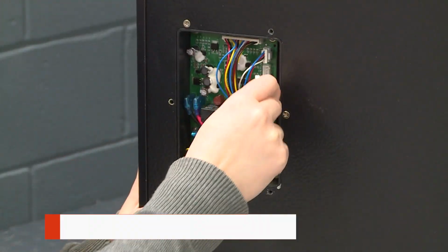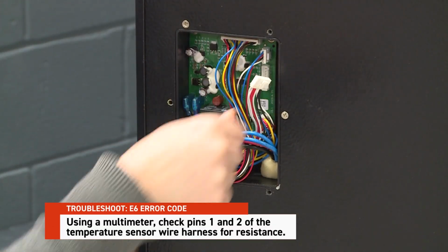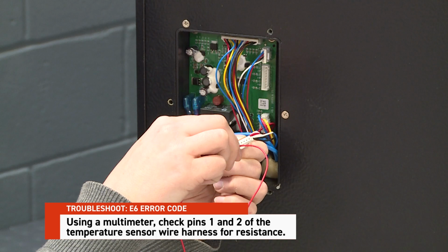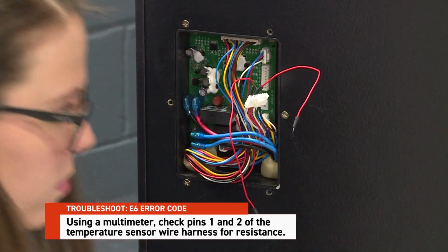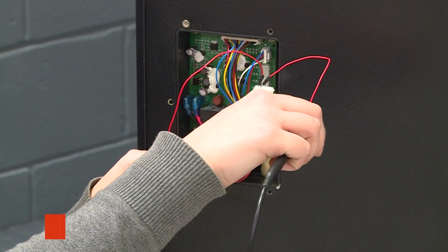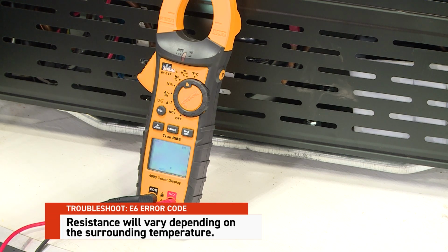To narrow it down, test the ambient temperature sensor. Locate the temperature sensor wire harness at the power board and disconnect it. Use a multimeter to check pins 1 and 2 of the harness for resistance. The resistance will vary depending on the surrounding temperature.